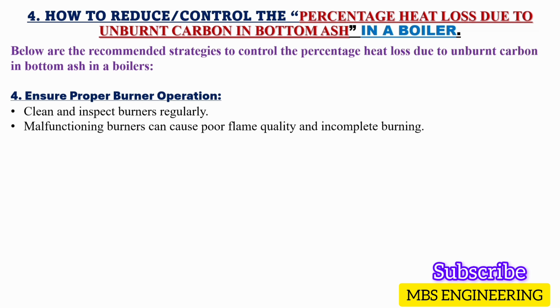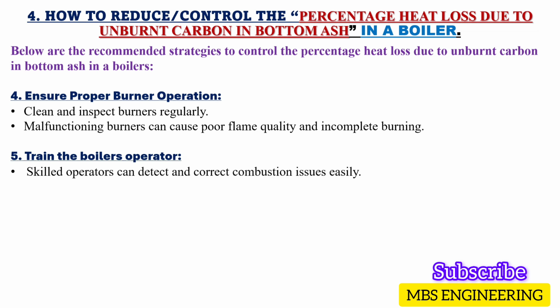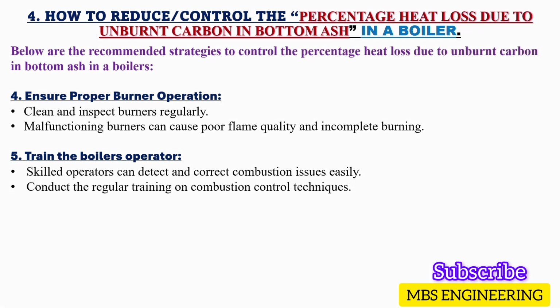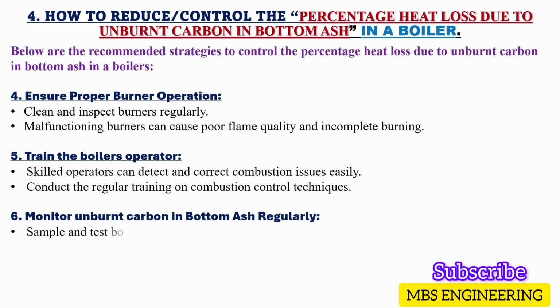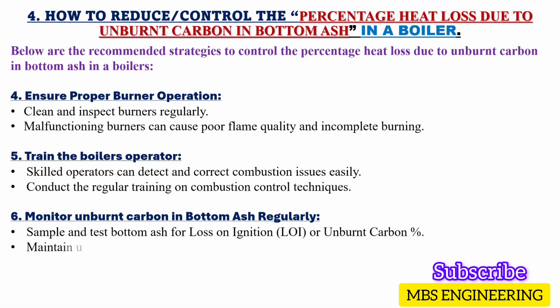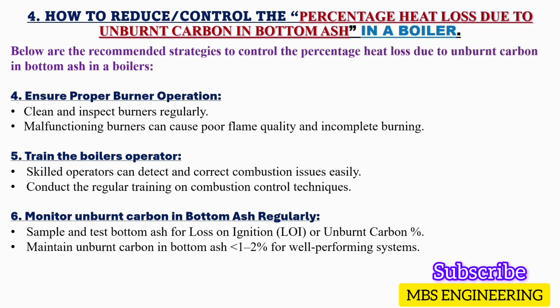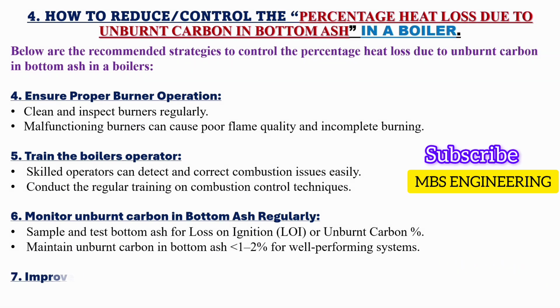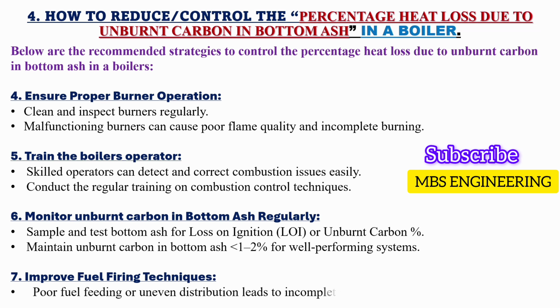The fifth recommendation is to reduce the heat loss to train the boiler's operator. Skilled operators can detect and correct combustion issues easily. Conduct regular training on combustion control techniques. The sixth recommendation is to reduce the heat loss to monitor unburnt carbon in bottom ash regularly. Sample and test bottom ash for loss on ignition, LOI, or unburnt carbon percent. Maintain unburnt carbon in bottom ash less than 1 to 2% for well-performing systems. The seventh recommendation is to reduce the heat loss to improve fuel firing techniques. Poor fuel feeding or uneven distribution leads to incomplete combustion.